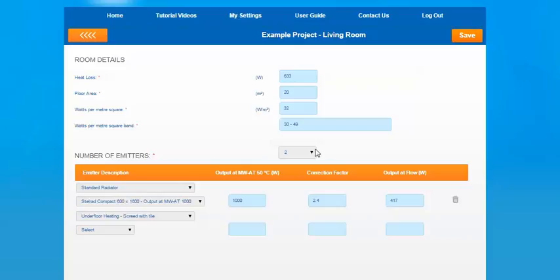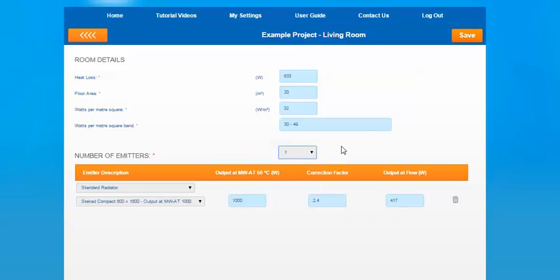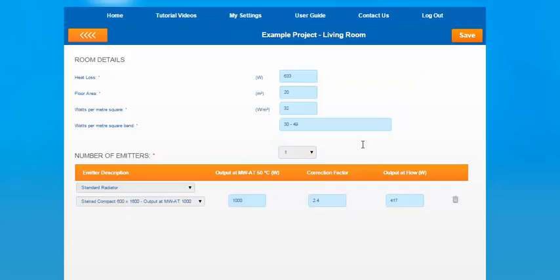That's basically a quick run through of that section. Obviously, if you have multiple emitters, just select them from the dropdown. One thing to look out for is the output of flow should meet the heat loss requirement of the room. As you can see from this example, one radiator wouldn't be sufficient to meet the heat loss of the room. So you would need to add another emitter, either another radiator or underfloor heating.